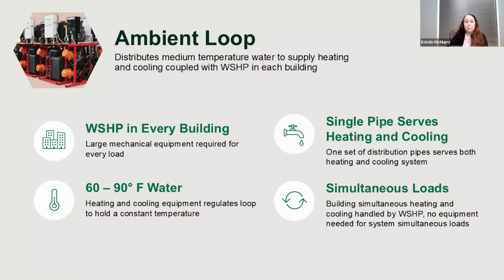That's the fairly big piece of mechanical equipment. From there, the temperature gets boosted up to be hot water or lowered down to be chilled water. It's a single pipe that serves both heating and cooling, and you can also do simultaneous loads from it. The water source heat pump in the building does simultaneous heating and cooling, with a similar COP to a heat recovery chiller, about 7.